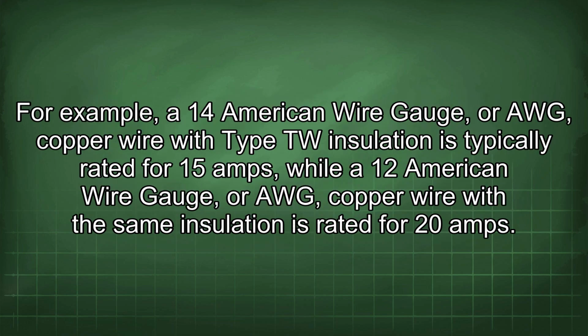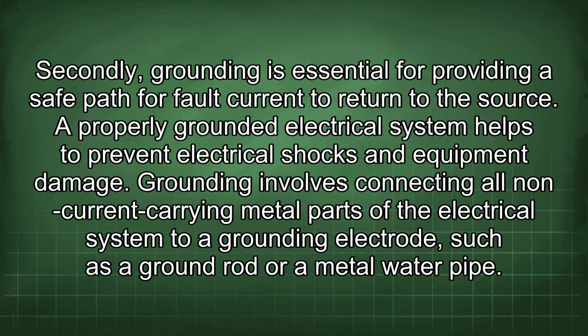Using undersized wires can lead to overheating, insulation damage, and even fires. For example, a 14 American wire gauge, or AWG, copper wire with type TW insulation is typically rated for 15 amps, while a 12 AWG copper wire with the same insulation is rated for 20 amps. Secondly, grounding is essential for providing a safe path for fault current to return to the source. A properly grounded electrical system helps to prevent electrical shocks and equipment damage. Grounding involves connecting all non-current carrying metal parts of the electrical system to a grounding electrode, such as a ground rod or a metal water pipe.